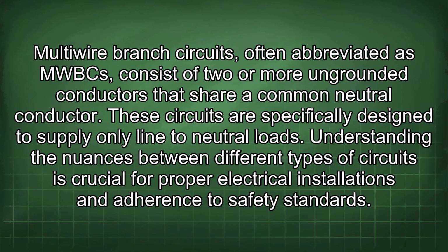Multiwire branch circuits, often abbreviated as MWBCs, consist of two or more ungrounded conductors that share a common neutral conductor. These circuits are specifically designed to supply only line-to-neutral loads. Understanding the nuances between different types of circuits is crucial for proper electrical installations and adherence to safety standards.